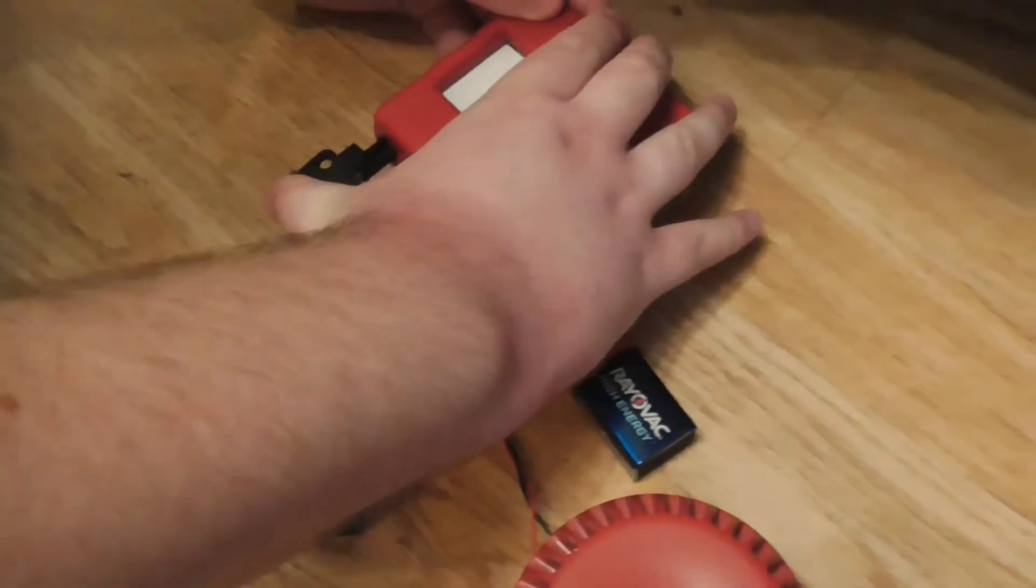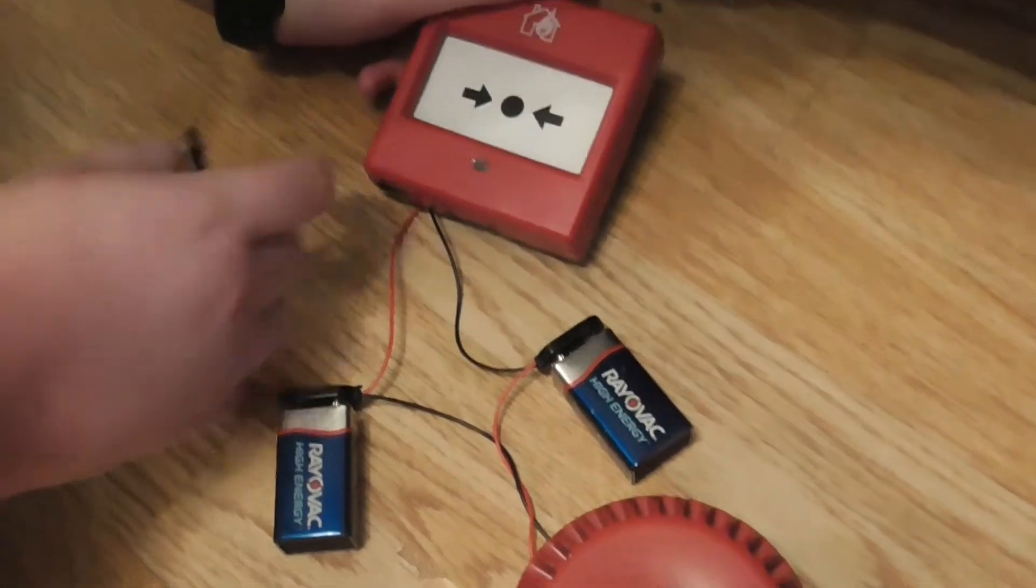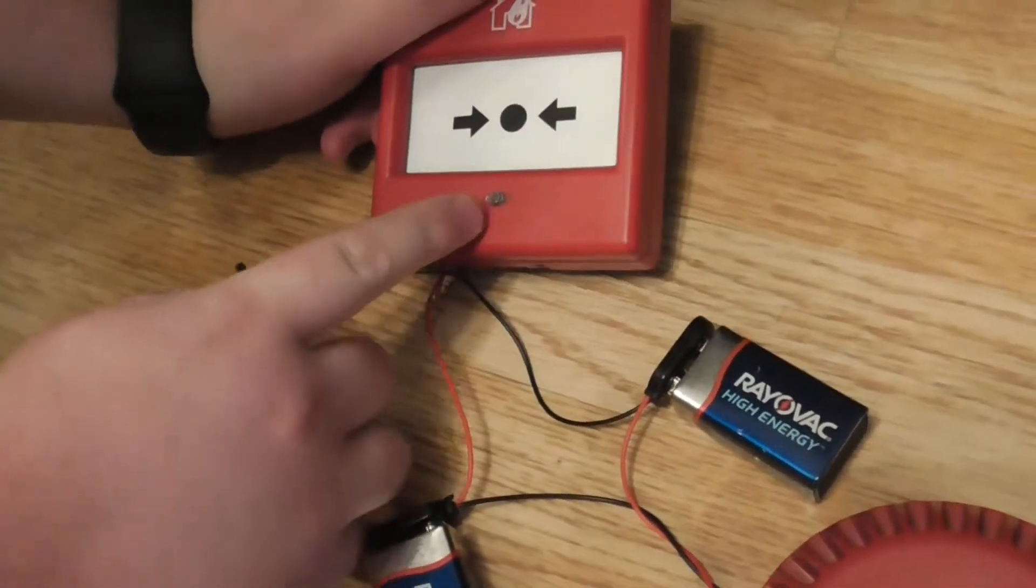So let's test the fire alarm call point. As you can see, the red LED illuminated and the sounder was on a continuous tone.